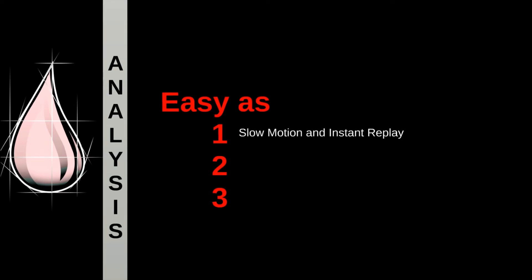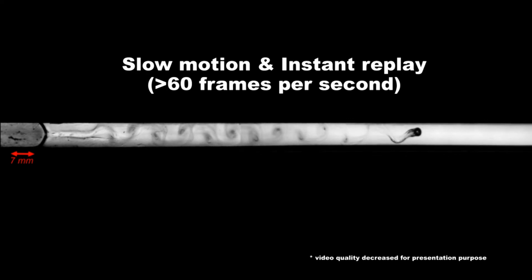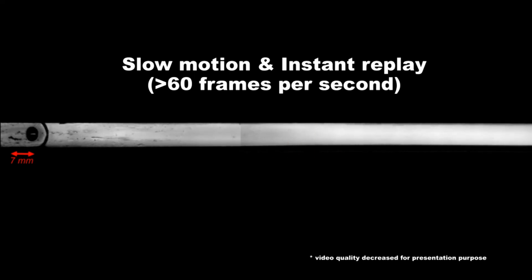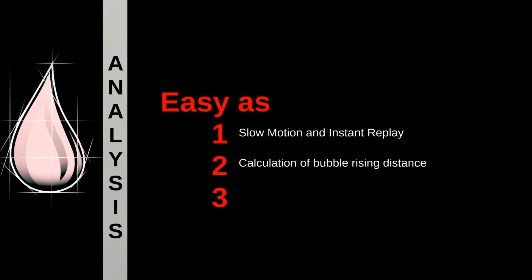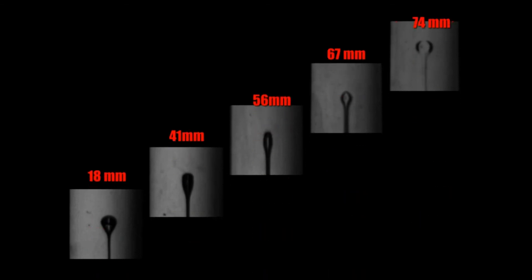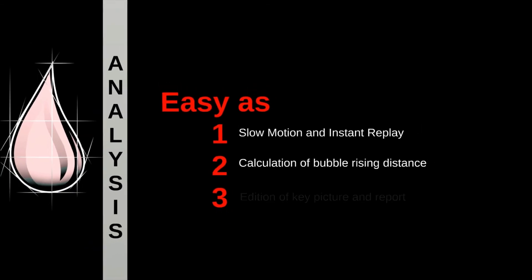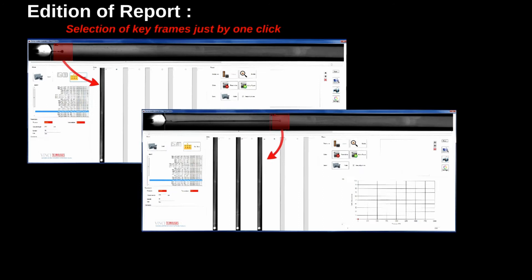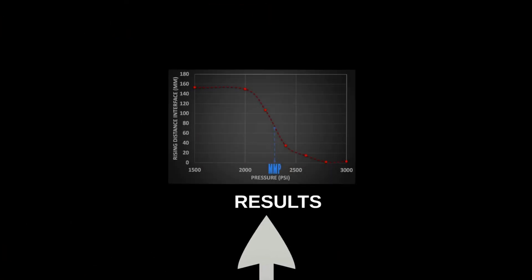After the experiment, all the movies are analyzed. The post-processing software enables slow motion and instant replay of all the steps. For example, here you can see a bubble rising above the MMP. Tail formation is easily visible thanks to the high-speed acquisition and LED lighting. The software also enables quick measurement of the rising distance of the bubble — at any step, the distance can be measured from the software. At the end, the operator can edit a report with the key pictures. For each movie, just by a click, the end user selects the relevant picture to include in the report. The software automatically generates a slideshow with the key frames, and the curve of rising distance versus pressure is also generated by the software to interpolate the MMP.